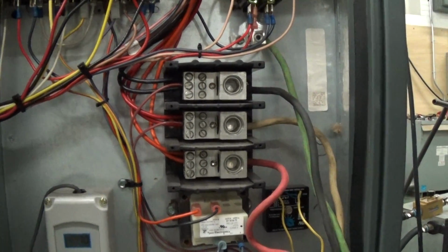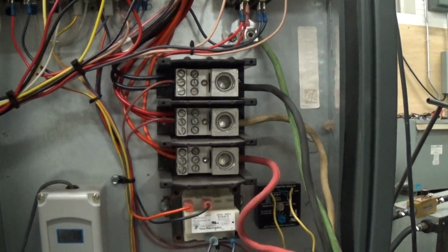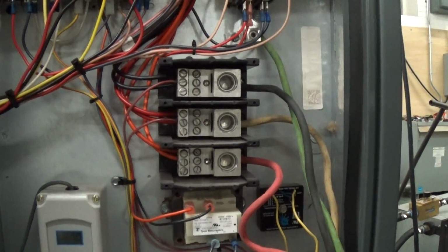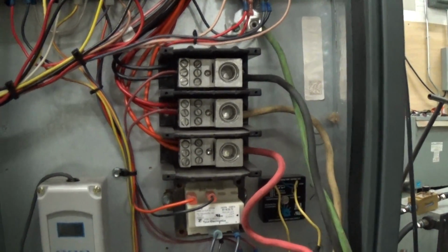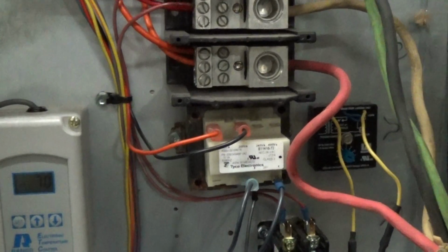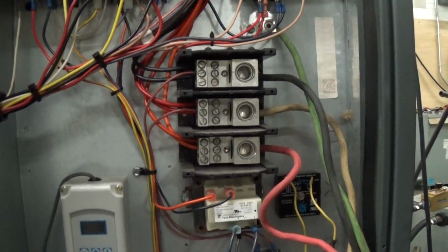It's a 4-wire connection, 3 hots and a ground. Okay, there's no neutral wire required. The control circuit is taken care of with the controls transformer that we see right there. So we're going to go even one step further here.